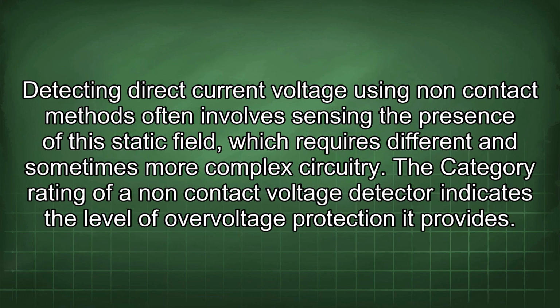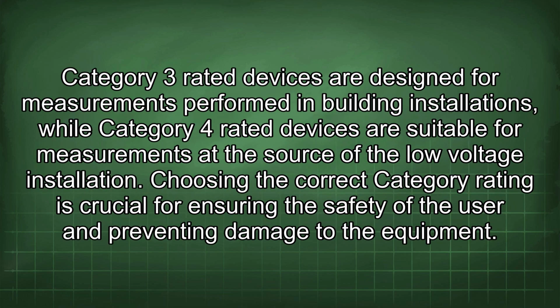Detecting direct current voltage using non-contact methods often involves sensing the presence of this static field, which requires different and sometimes more complex circuitry. The category rating of a non-contact voltage detector indicates the level of over-voltage protection it provides. Category 3 rated devices are designed for measurements performed in building installations, while Category 4 rated devices are suitable for measurements at the source of the low-voltage installation. Choosing the correct category rating is crucial for ensuring the safety of the user and preventing damage to the equipment.